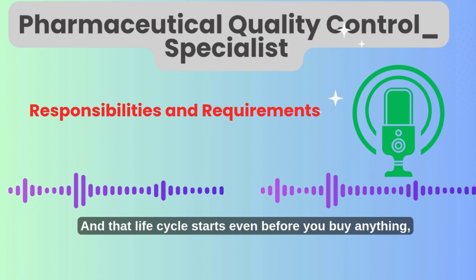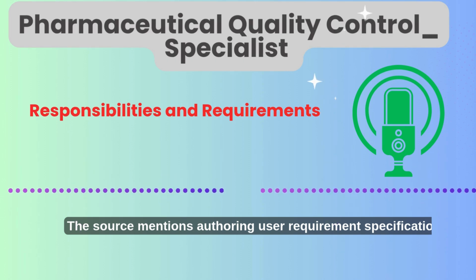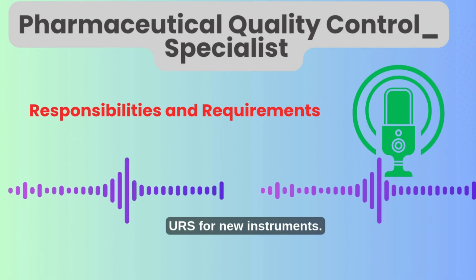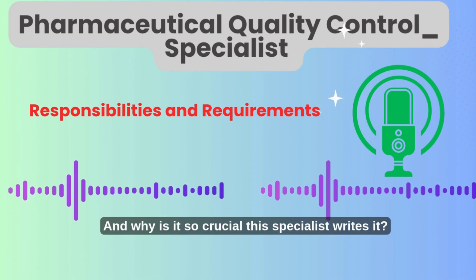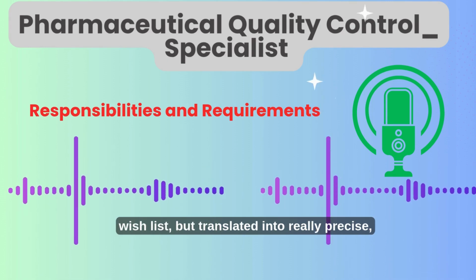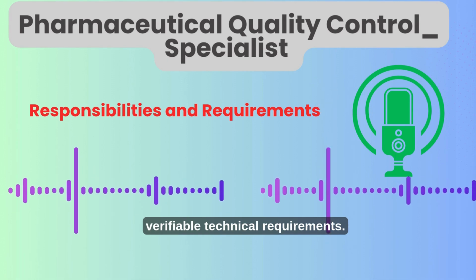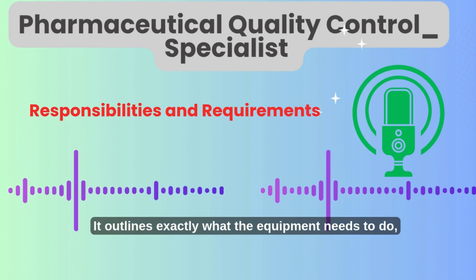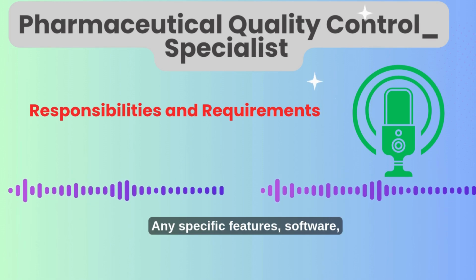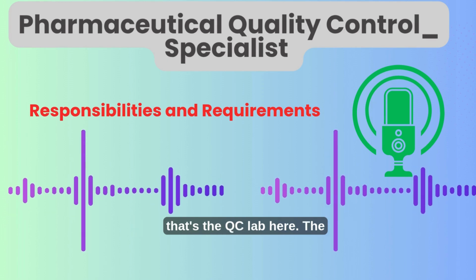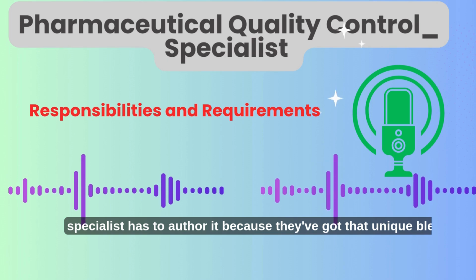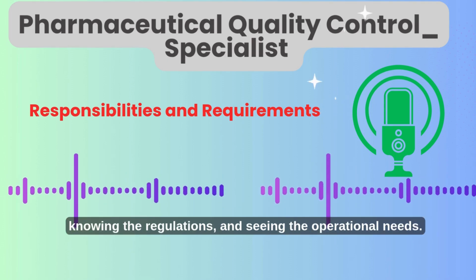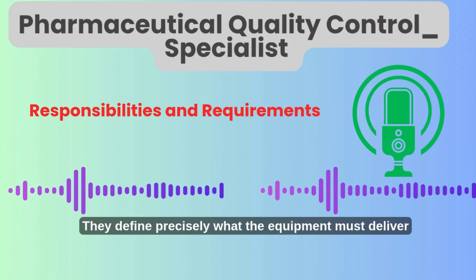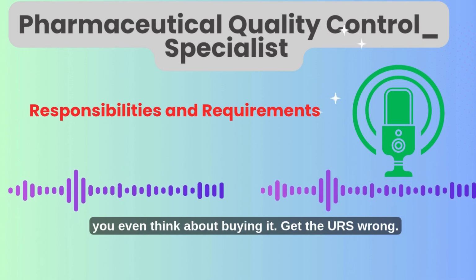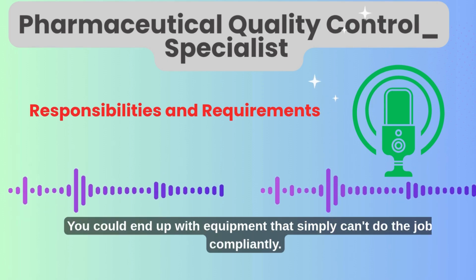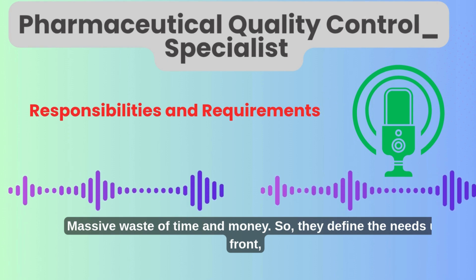It's critical. And that life cycle starts even before you buy anything, with deciding what you need. The source mentions authoring user requirement specifications, URS, for new instruments. What exactly is a URS, and why is it so crucial this specialist writes it? Think of a URS as like the definitive wish list, but translated into really precise, verifiable technical requirements. It's a detailed document. It outlines exactly what the equipment needs to do, how it must perform under different conditions, any specific features, software, constraints required by the end user, that's the QC lab here. Okay. The specialist has to author it because they've got that unique blend of understanding the analysis, knowing the regulations, and seeing the operational needs. They define precisely what the equipment must deliver to meet QC's needs and comply with regulations before you even think about buying it. Get the URS wrong, big problems later. Huge problems. You could end up with equipment that simply can't do the job compliantly. Massive waste of time and money. So they define the needs up front.